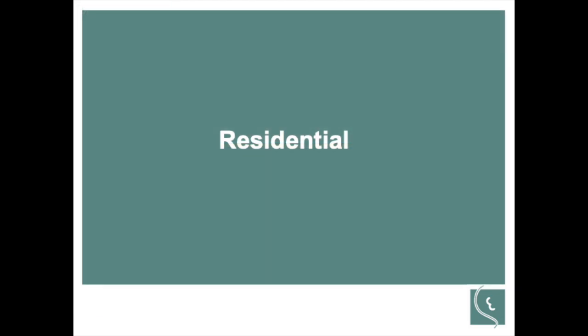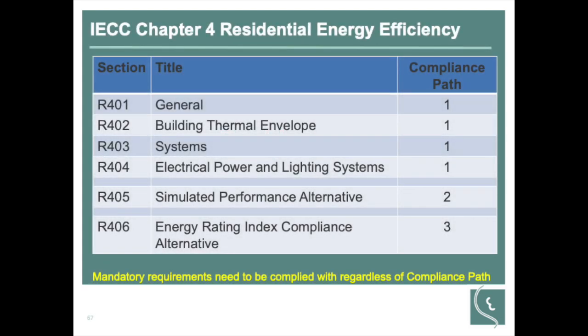So as far as residential, there's a couple of different compliance paths. First is our prescriptive path, which is our sections 401 through 404 that we talked about earlier. Number 2 is the simulated performance path. This would be using certain software packages. This is not ResCheck. ResCheck is compliance path 1. Simulated performance might be a Trane TRACE, an eQuest, any number of the DOE energy modeling softwares. And then the third is the ERI, the Energy Rating Index, a close cousin of the former RESNET.